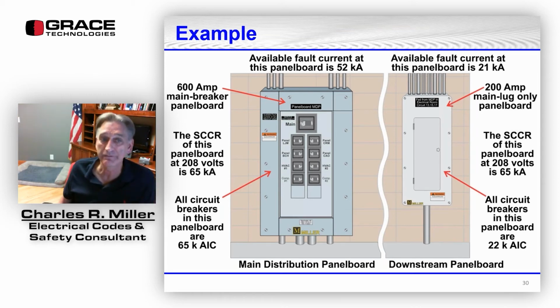Downstream from that, the available fault current in that panel board drops to 21,000 amps. It is a 200 amp main lug only panel board. The short circuit rating of that panel board is also 65,000 amps. The breakers in there, because the available fault current has dropped down to 21,000 amps, 21 kA, only have to have a 22 kAIC rating.